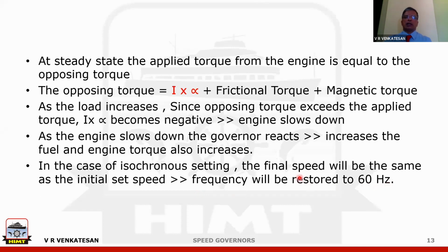What I am trying to tell is that whether you have an isochronous setting or some droop, the governor will handle additional load. As more load is brought in, the governor will definitely increase fuel for the engine, and the generator engine will be able to supply power for the additional load. The difference lies in what speed is maintained. If you have an isochronous setting in the governor, then the initial speed will be maintained throughout. If you allow droop, then as the load increases, frequency will come down.